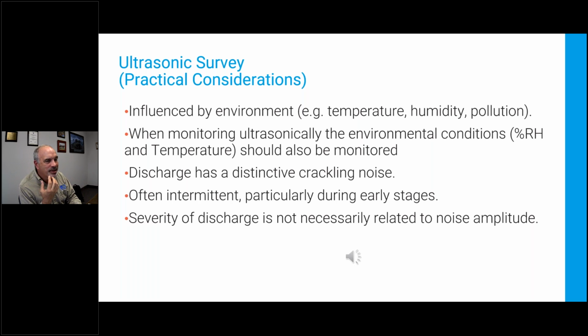It has a very characteristic sound. Once we've brought it down into the audio band, it sounds like, amazingly enough, what you would expect it to sound like. It sounds like crackling, buzzing, arcing, sparking, bacon frying, exactly what you'd expect. In the beginning, it may come and go with humidity. It may come and go with voltage, but as it gets worse, it's going to be less intermittent. And then the bad news is the number you're going to read off the instrument doesn't mean much. The severity of the discharge is not necessarily related to the noise. So I put my hand up in front of my mouth and keep talking. You will notice you will measure a reduced level, even though the discharge had not changed.